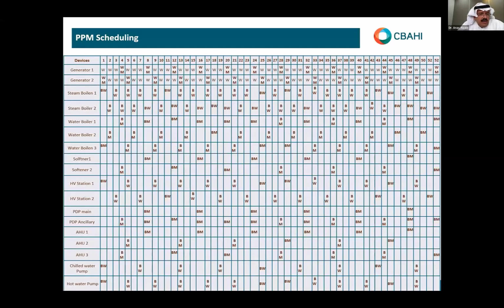PPM scheduling - if you have generators, air handling units, you need to put a schedule for the whole year. You go and review it; the guy responsible is the FMS. If you don't have one, you need to discuss it with your contractor, and make sure that PPM scheduling is done monthly or weekly, depending on the type of machines - air conditioning, water pumps, heating systems, autoclaves, sterilizers, X-ray machines, all medical and non-medical equipment. You need a full PPM schedule for all of it, and we as CBAHI surveyors need to see these documents to confirm proper PPM is being done.